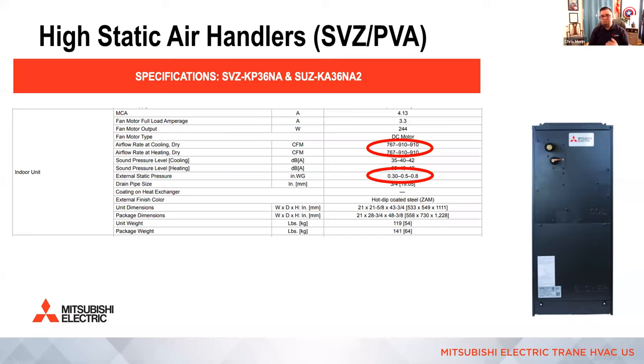All right. So same with design principles here. The medium speed with a medium static pressure is what we would design around. So in this example, we would choose 910 CFM and 0.5 inch of static, 0.5 because that's medium. And it gives our technicians the ability to turn it up or turn it down if it's too noisy or it can't be balanced, or the design of the ductwork couldn't be perfect when you actually applied it to the house when it goes to be installed, right?